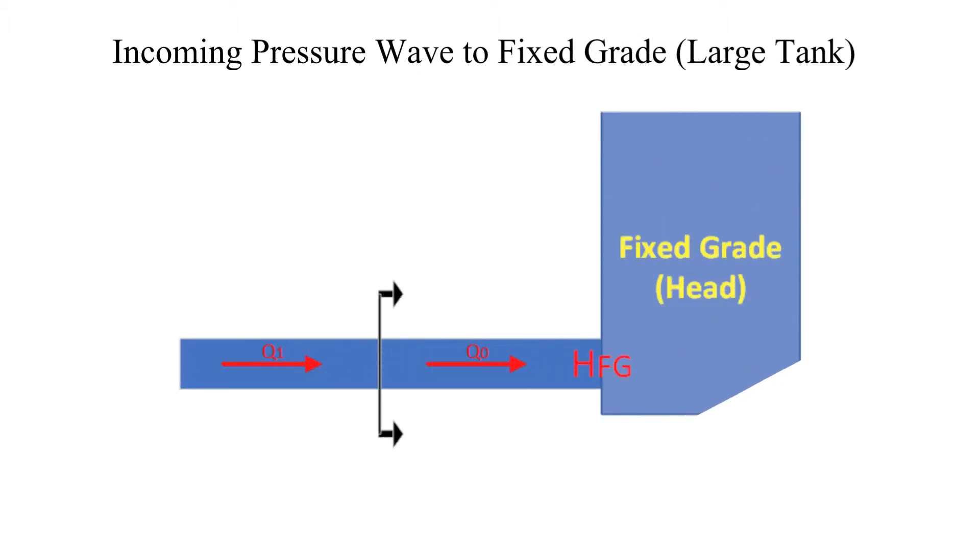Let's start with how a wave reflects off a large tank. Shown is an incoming wave denoted as delta H1 prior to it impacting the large tank. Note that the head after the wave is the original head plus the magnitude of delta H1. The flow after the wave is denoted by Q1, H0 and Q0 are the head and flow in front of the wave.